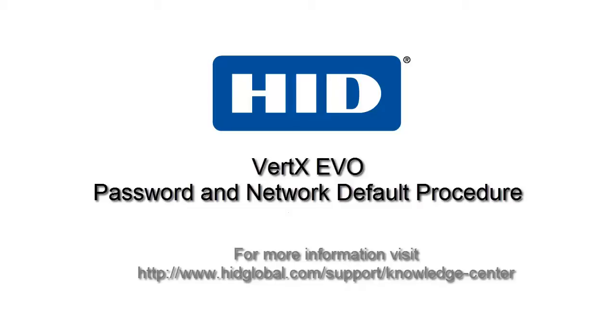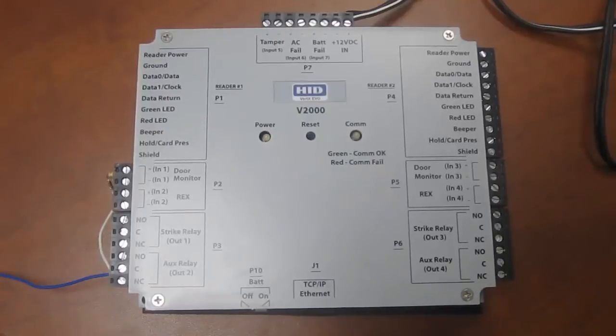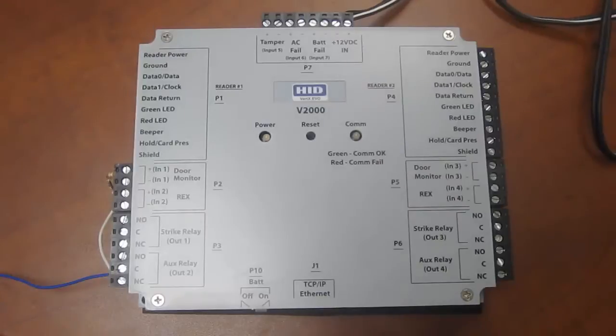This is a VertX EVO password and network default procedure. This procedure is valid for HID Global's VertX EVO, V1000, or V2000.